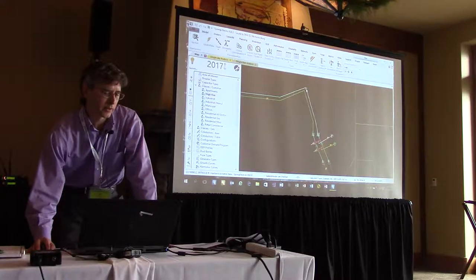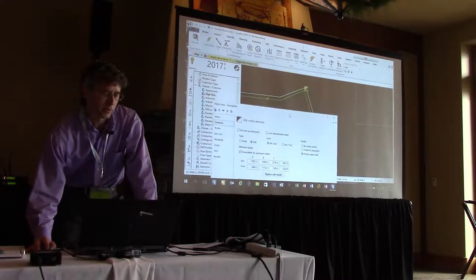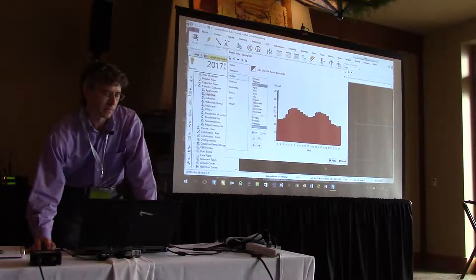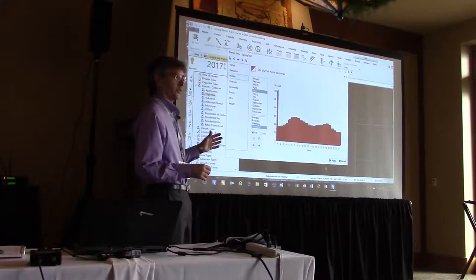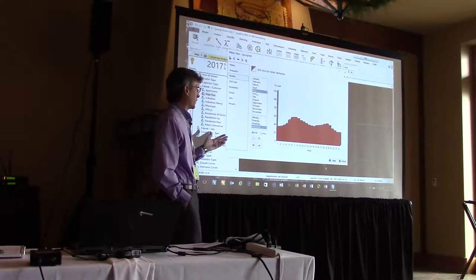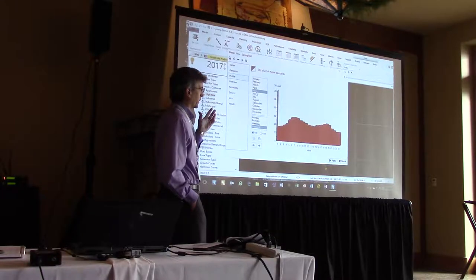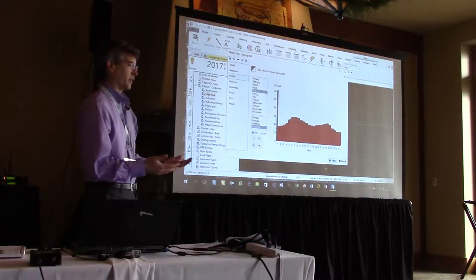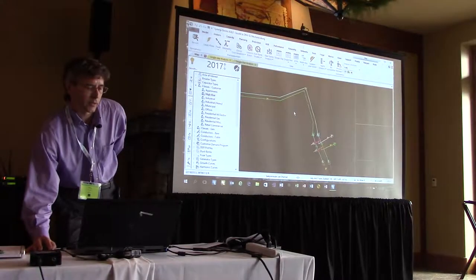It's up to you what kind of detail is in there. One tool is customer class curves, but another tool I recommend — if you don't have time-of-day modeling in your system — is to use feeder demand curves. If you go into a meter and say you want to use a profile, this is my feeder meter right here. Now we've got this thing where we can actually have the months of the year put into this profile. With this activated, your whole feeder is going to follow that curve.